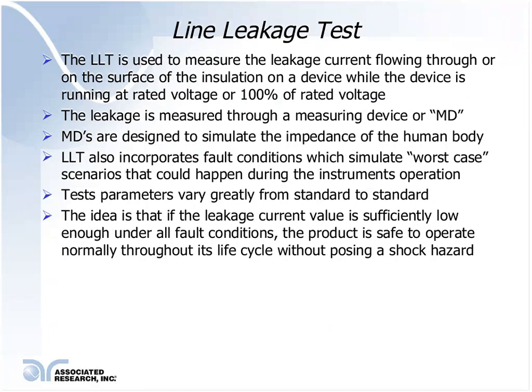Next, we're going to get into the line leakage test. We're going to briefly review what the line leakage test is, and then we're going to go into how the line leakage tester can be verified. Now, from what we remember, the line leakage test, just like the Hipot test, measures the current flowing through or on the surface of the insulation on a device under test.